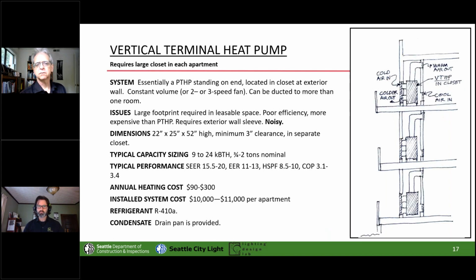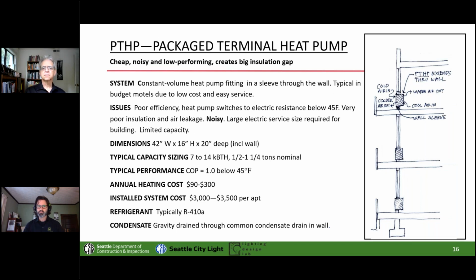Is there on the previous technology, that package terminal, is the COP any higher or different before the toaster kicks in? Yes. It's using a heat pump above 45, but the heat pump is super limited. We'll talk a little about why later. So it gets down to 45 and it says, all right, I'm done, I don't work anymore. And you think of what are the hours that we need heating in this climate? I think the average temperature year round is 47 in Seattle. And so for basically the entire winter, you're at the toaster oven thing, right? Maybe, considering this is Seattle, some of our summer mornings too.